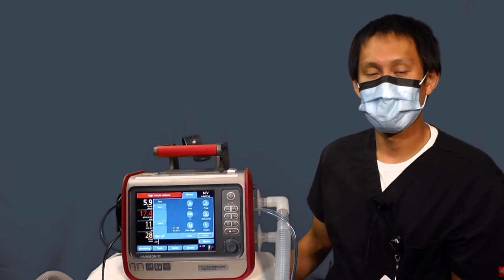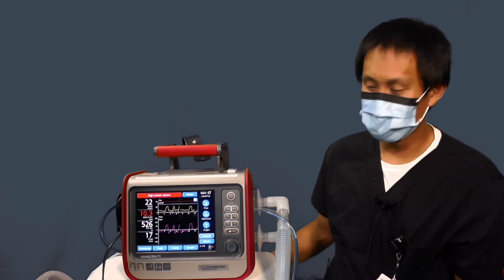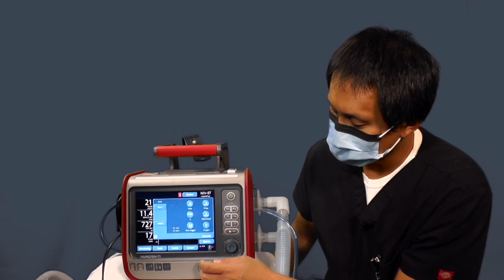You'll have to find the tidal volume by setting your pressure. So an easy way of doing that is look at the pressure that is set on the hospital BiPAP machine, and then take a look at what the peak pressure is, and kind of start from there to see what kind of tidal volumes you're getting. Otherwise, you should be able to copy all the settings from the hospital AVAPS mode over to your ventilator. For your P max and your P low, those are essentially your pressure limits, which you can place into your alarm settings. And then otherwise, everything else can be copied over. Your I time, your rate can be copied over to this machine.